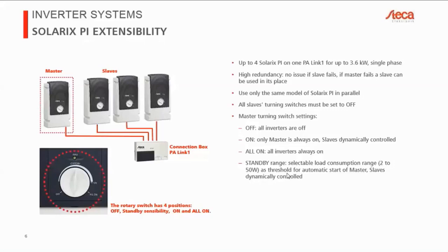So what really happens is the inverter is sending out a sine wave once every second, just one wave or 1 or 2 wave packages, and it's checking if there is an AC load connected somewhere on the system. If there is an AC load connected, and if the AC load is consuming more than this threshold that you can control with a switch, then the inverter automatically starts up and does its job. So this is another way to reduce the consumption, the self-consumption, even further.